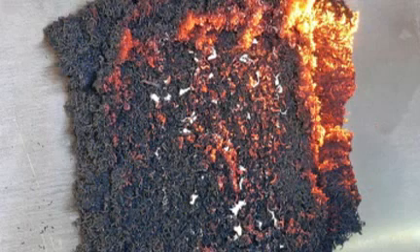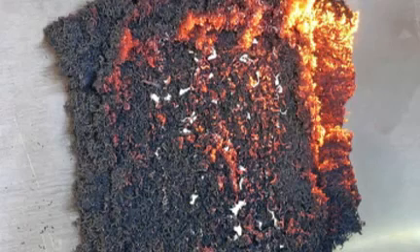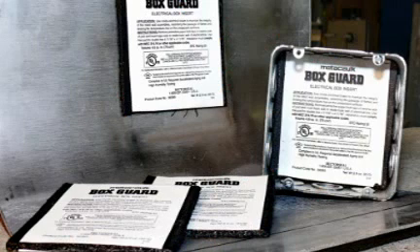While the test assembly is heating up, we'll take a closer look at how this char stops the spread of fire and toxic smoke. We'll use a sample of MetaCaulk box guard, designed for fire stopping electrical boxes, to illustrate the process of intumescence — the ability of some fire stop materials to expand when heated. Watch as we heat this one-quarter inch thick sample of a box guard. As the torch applies heat, the intumescent properties of the product cause it to expand up to 37 times its original thickness and form a strong insulating char. We'll also test the box guard inside an electrical box using time-lapse photography, showing the tremendous expansion that takes place in 5 minutes of direct heat.